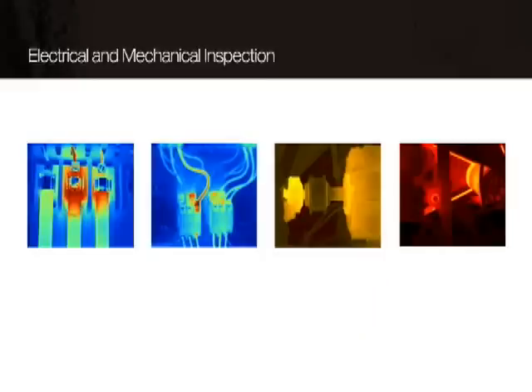The IR image will reveal hot spots in the system, verifying problems like unbalanced and excessive loads, loose connections, or misaligned parts.